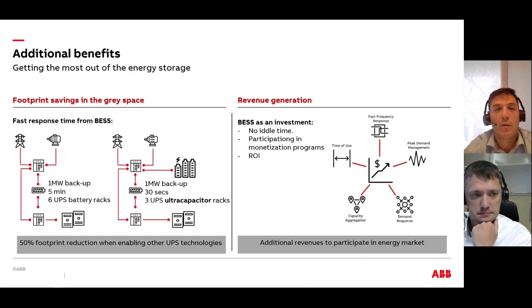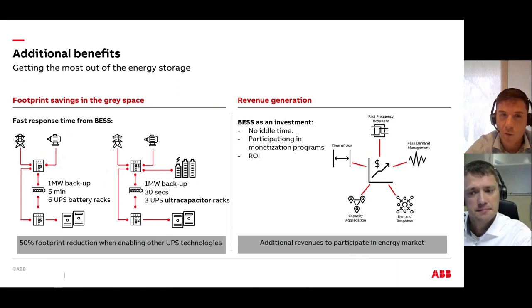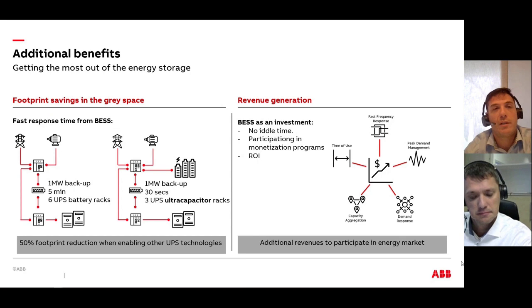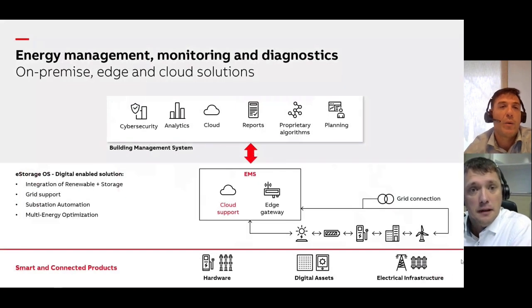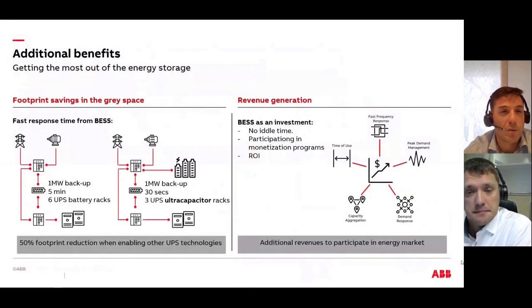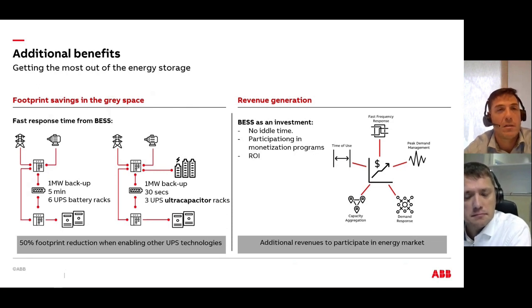If we have the BESS, as we said, we can pick up the full load, breakers opening, islanded operations within half a second. So we do not need the range of minutes. In order to get a backup power of 1 megawatt and 30 seconds to be on the safe side, we can change the technology that is on the energy storage of the UPS, and we can move to ultracapacitors. If we move to ultracapacitors, we jump from 6 battery racks to 3 ultracapacitor racks. So we have a 50% footprint reduction when enabling other UPS technologies.